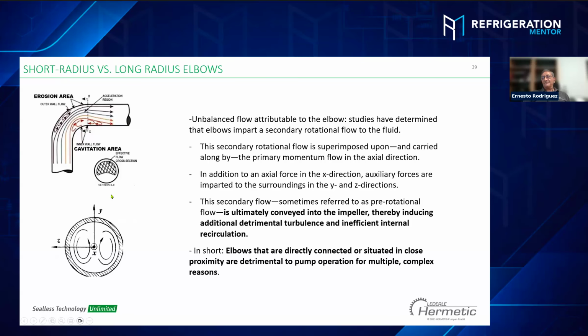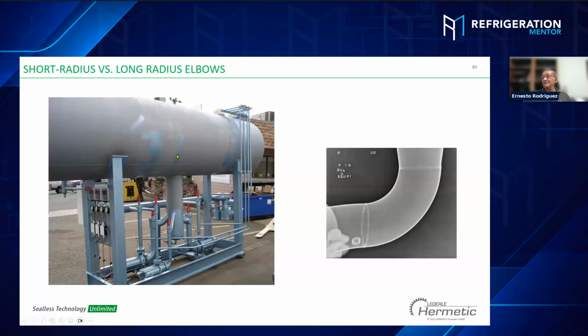Okay, one more issue: elbows. Elbows create turbulence. Short radius elbows have this turbulence going back to the pump. We don't need elbows. I don't agree with having elbows on the suction of the pump. We have this sample right here. I think this manufacturer used a long radius elbow because maybe there was no other option. It's going to work, but I don't agree too much.